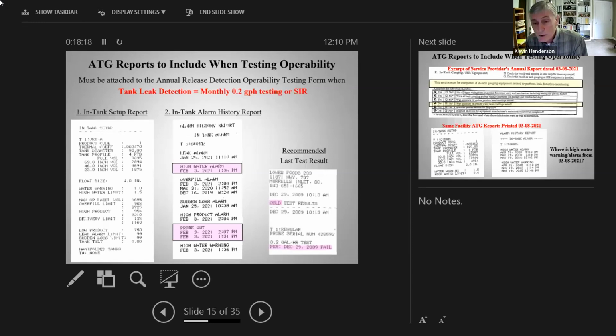Mark has mentioned this already, of course. The one thing I would mention about including these Veeder-Root reports is that you do not want to rely on the little tape itself to be a permanent record. These are thermal printers on these tank gauges. Of course, that's thermal paper, so you know what that means. If that little printout lays out in the light, or the sunlight in particular, it will very quickly fade away. UV light will quickly destroy these reports.